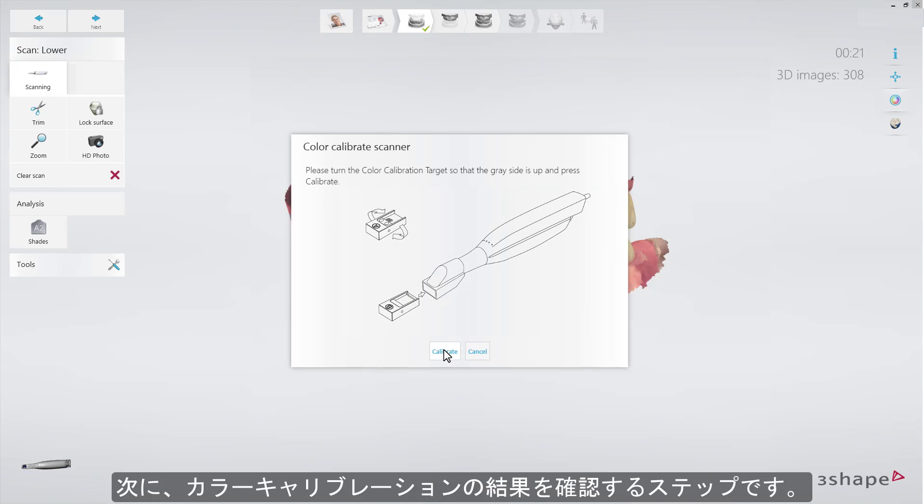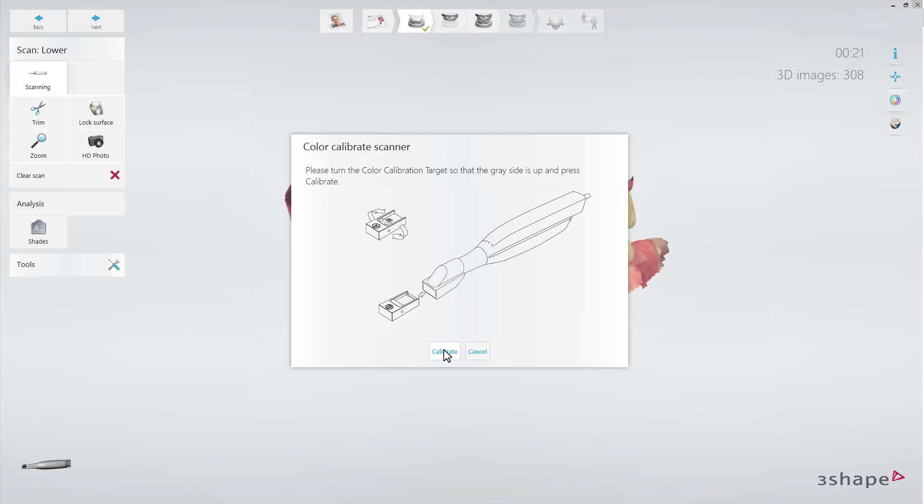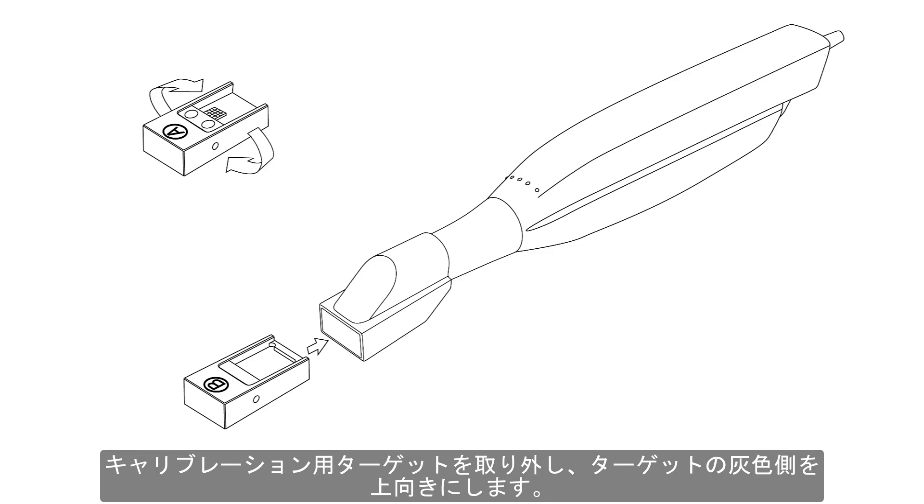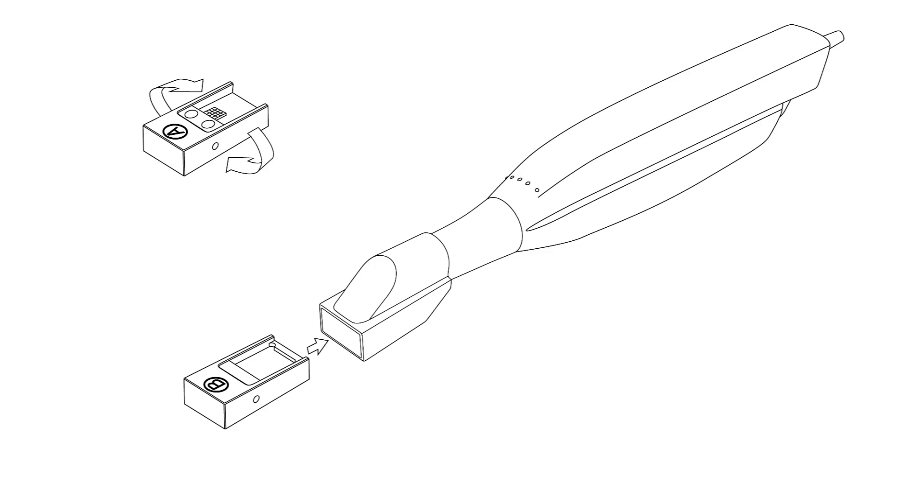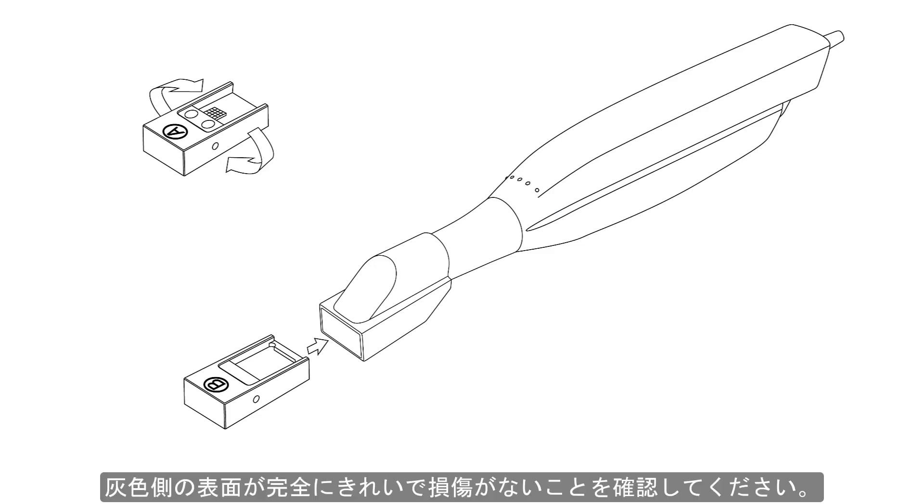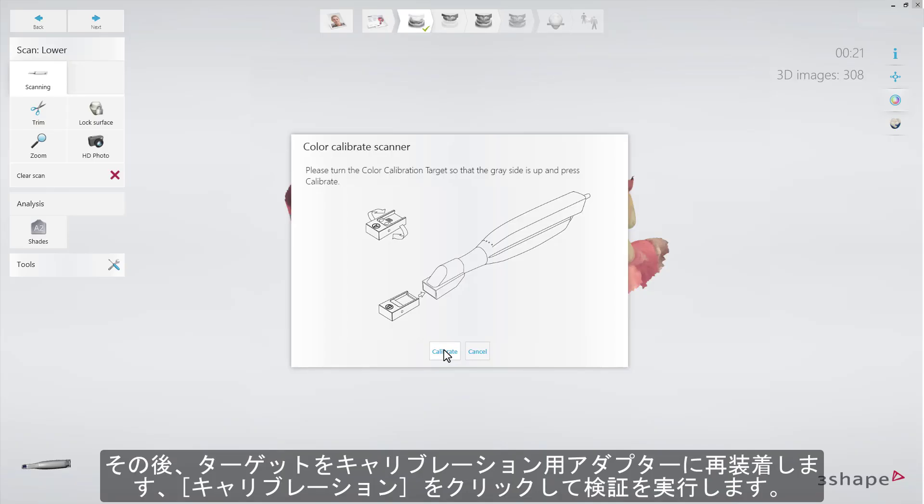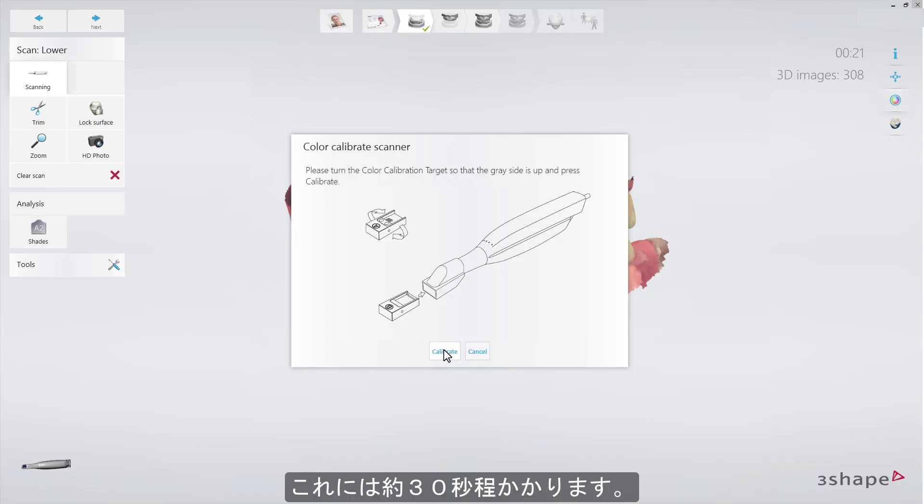The next step is preparing for validation. Detach the color calibration target and turn it over to face upwards on the gray side. While performing this action, make sure that the gray surface is perfectly clean and free of scratches. Upon doing so, reattach it to the color calibration adapter and press Calibrate to start validation. It takes around 30 seconds.